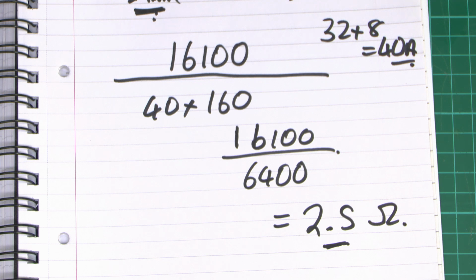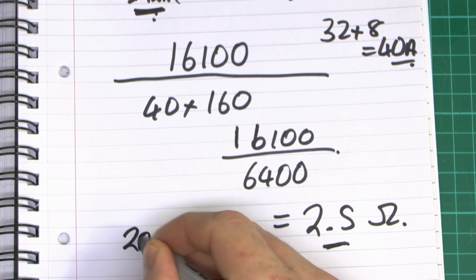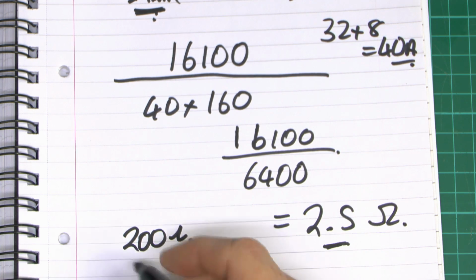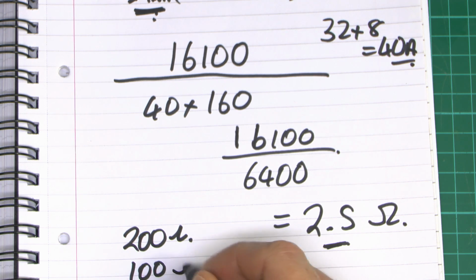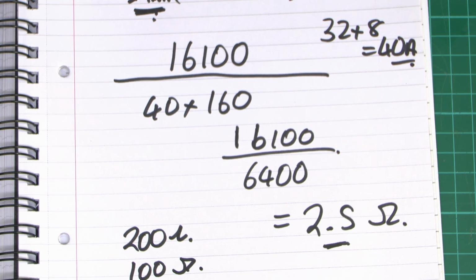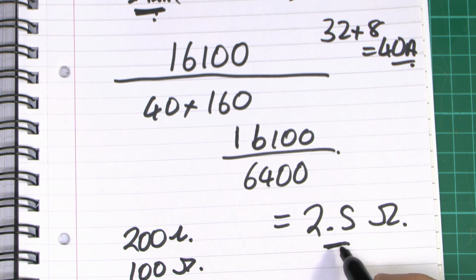Now, if you're going to put an electrode in the ground, good luck getting anywhere near that, because in most cases that's actually going to be next to impossible. Bearing in mind for the rest of the regulations, a typical value for an electrode is in the region of 200 ohms or less, and in some cases maybe in the region of 100 or so. And if you're actually going to put these things in practically, it's generally relatively easy to get in the region of 50 ohms or so. Not really a problem. But getting down to 2.5, well, that's next to impossible. You literally have to be digging up the entire garden and putting in a huge grid or mesh underground, and possibly encasing it in concrete as well, and who knows what other bother.